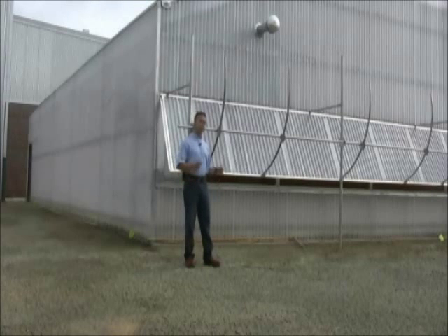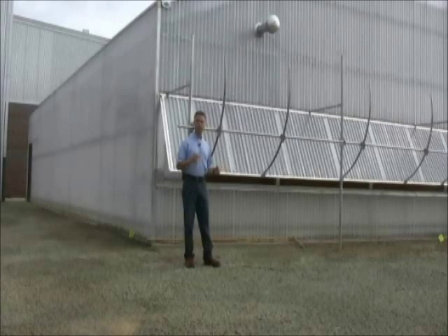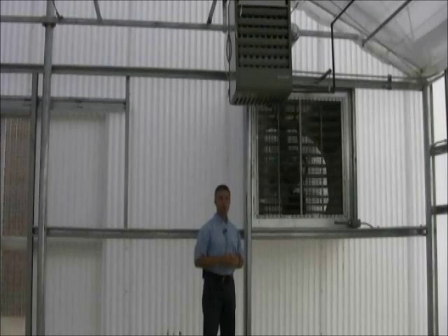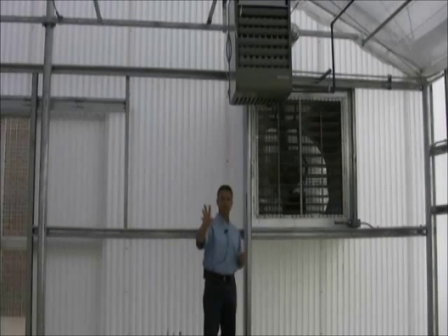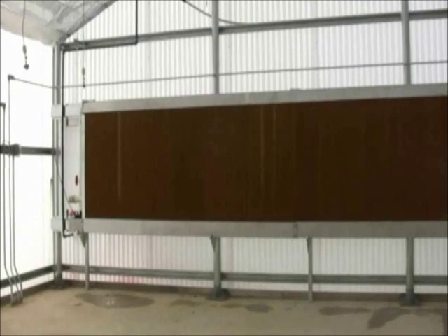If your goal is to lower the inside temperature of the greenhouse to a point below the outside temperature, then that's most commonly going to be done with evaporative cooling. With this type of mechanical ventilation, hot air is being exhausted out of the greenhouse with these fans, while at the same time air is being pulled from outside across the cool pads on the opposite end of either an end wall or a sidewall. It's being cooled as it enters the greenhouse.